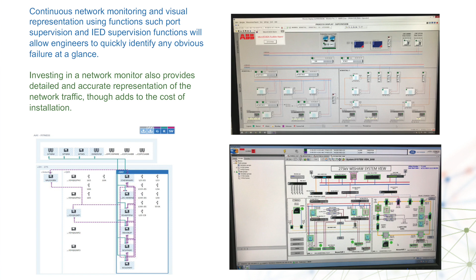It takes a bit of time to create a port supervision screen like that, but when your maintenance engineer walks in, he has first-hand information from this screen if something has gone wrong. For example, if this merging unit loses time sync or has a bad quality, it will show here. So it's just right there. You don't even need to think about it much. You can see it on the screen, and then you start your investigation from there.